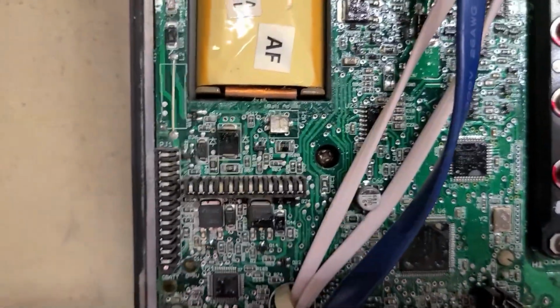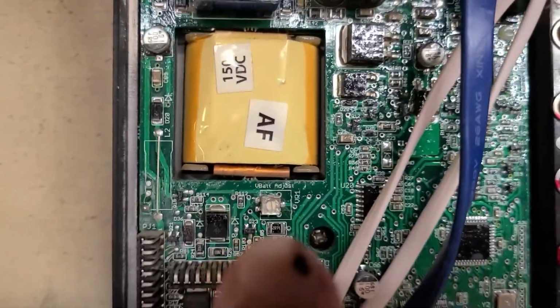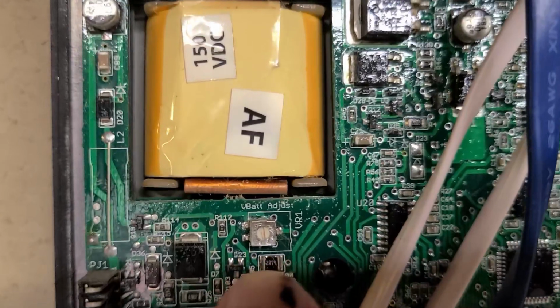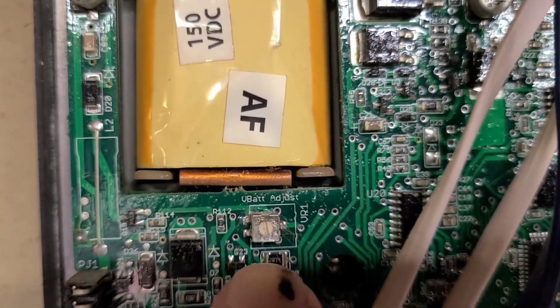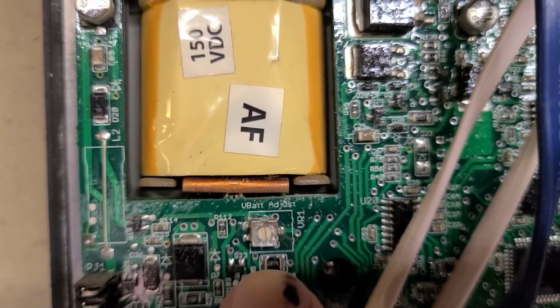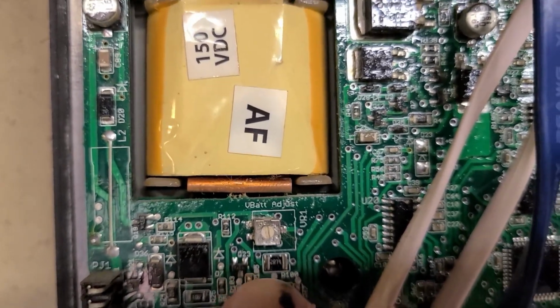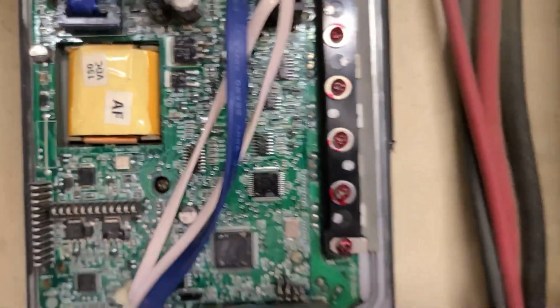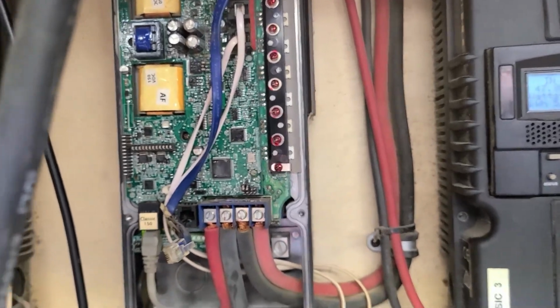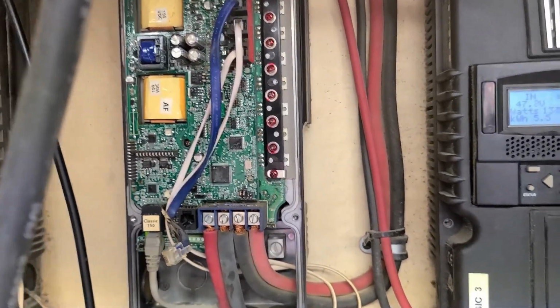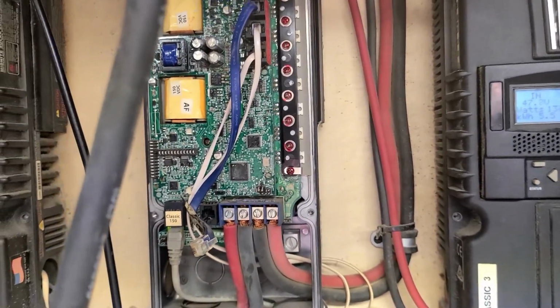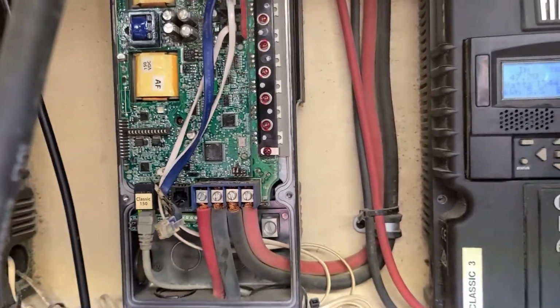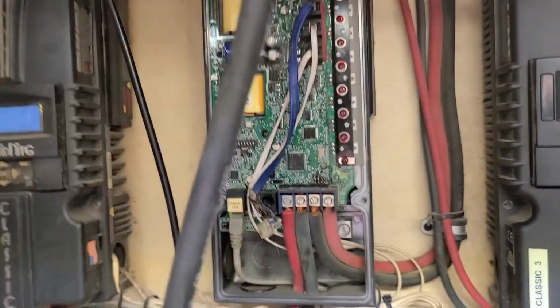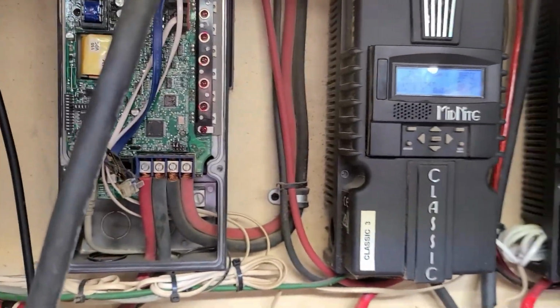So right there, once again, that says voltage battery adjust - that's where you want to use it to really fine tune and calibrate your systems. Remember, have your voltage tweak setting inside your charge controller, where it says -1, -2, make sure those are set at 0, so everything gets tweaked just right amongst your charge controllers.